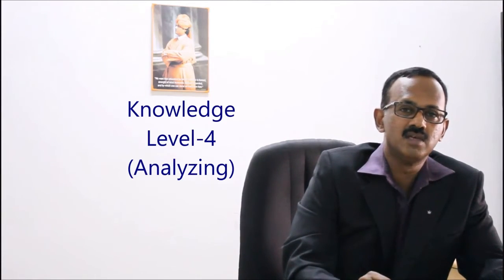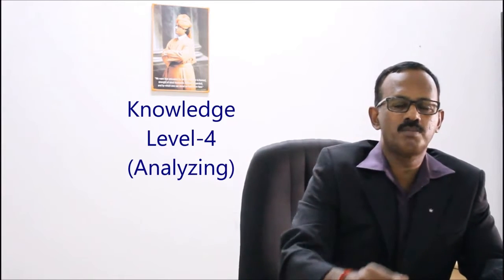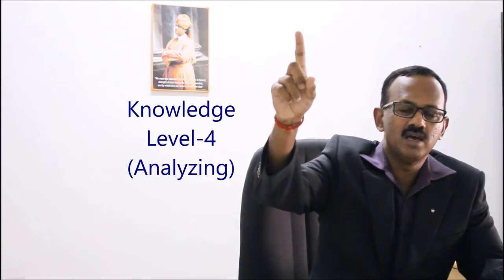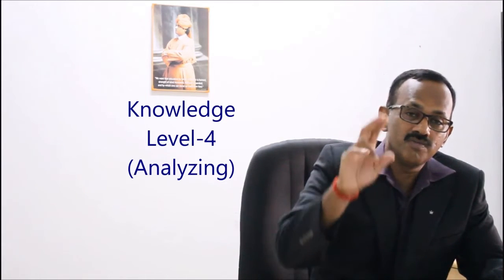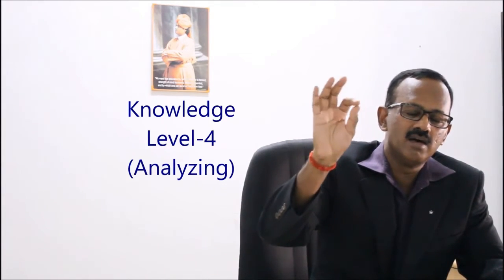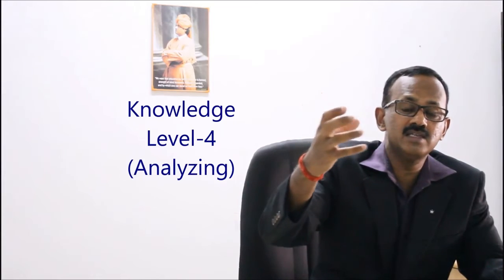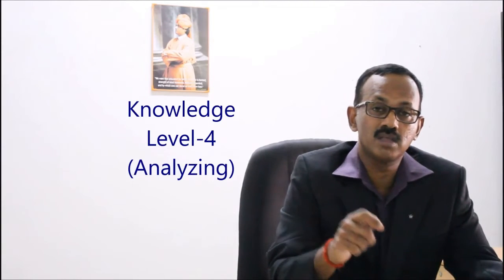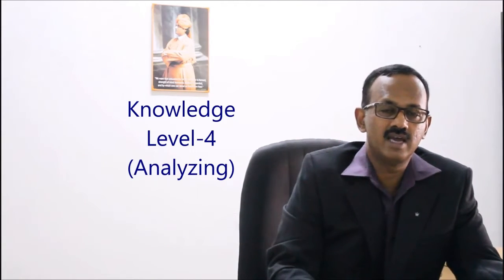then we can say that the learner is very good in analyzing. For example, if a 1 kg weight is thrown on the platform of a digital weighing scale, it will be an impact load, and automatically it will have an effect on the final output displayed on the digital scale. Now, if the digital scale is maintained at room temperature, maybe the reading might be proper. If you increase the temperature around the digital weighing scale, even if the input is given properly, the output will get affected. Therefore, the temperature around the digital weighing scale has an impact on the scale reading.